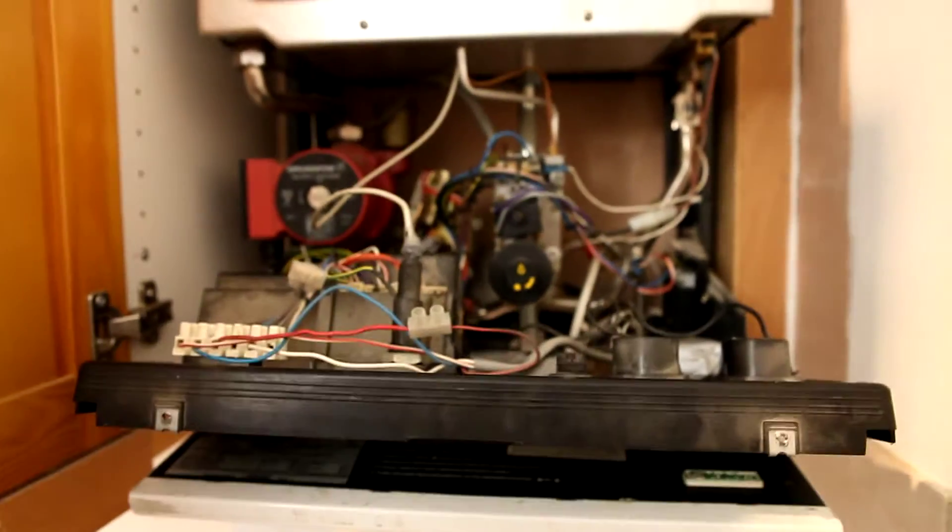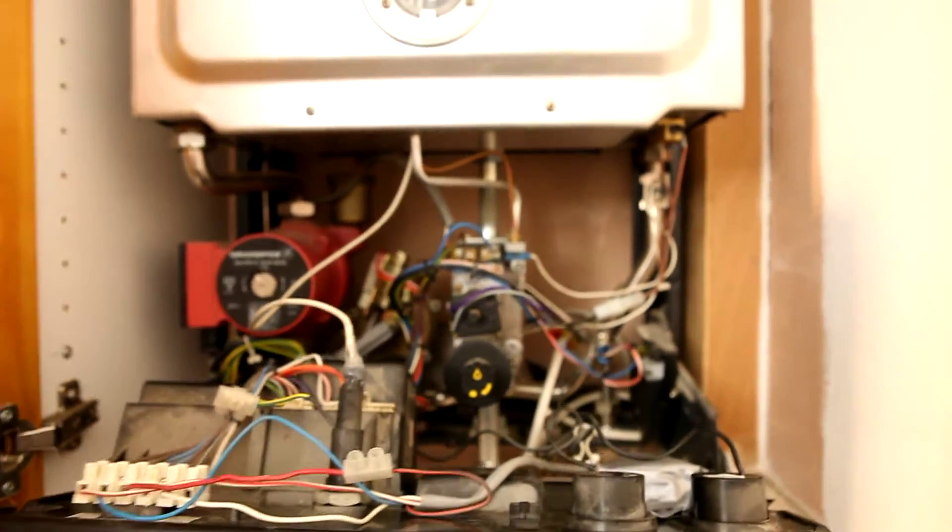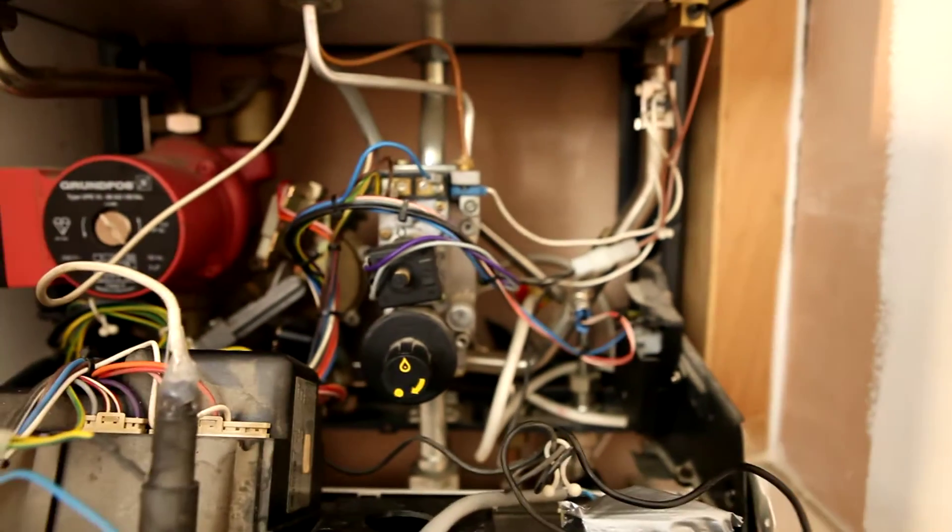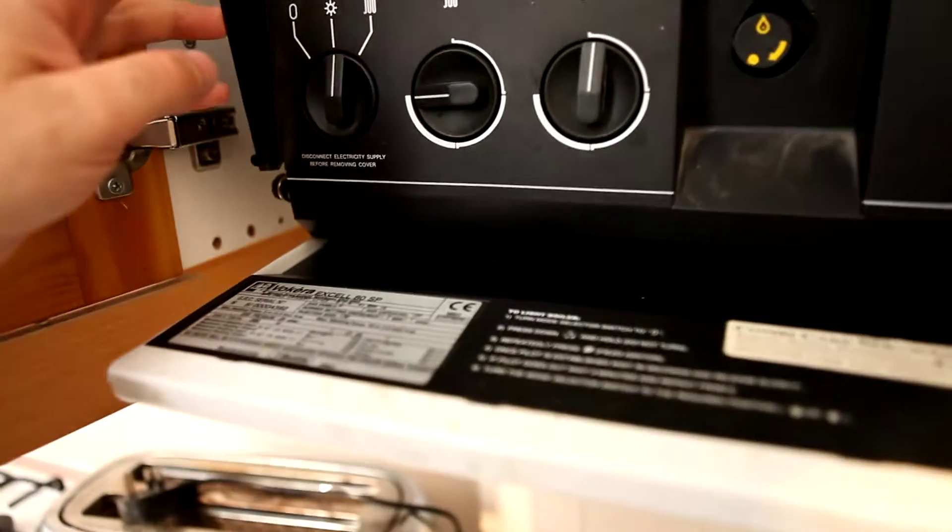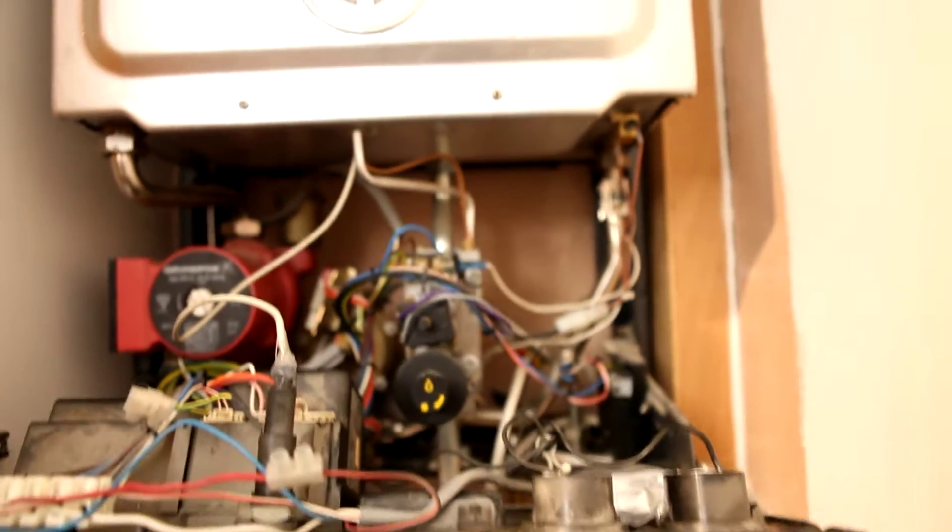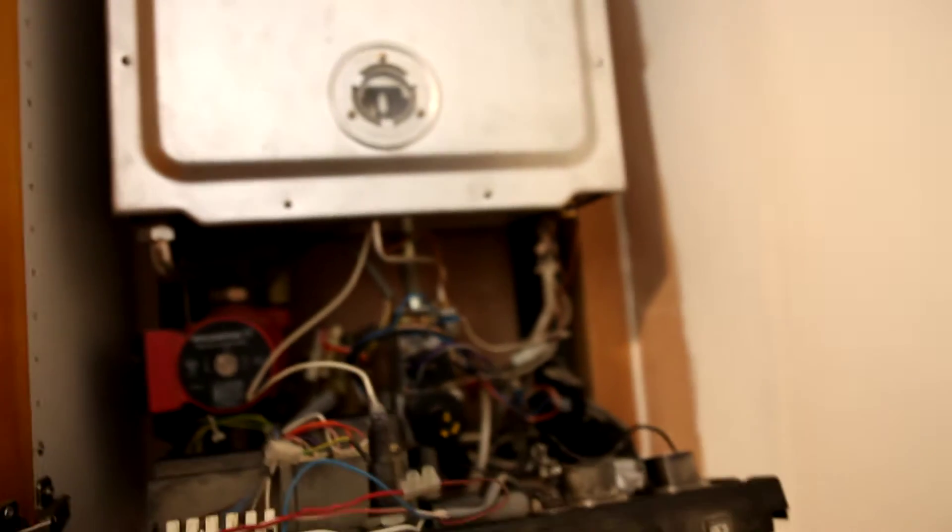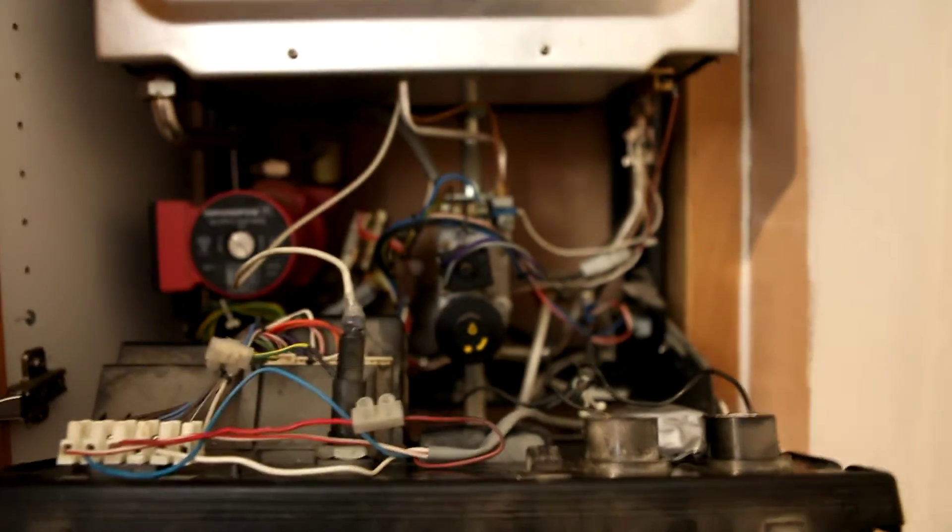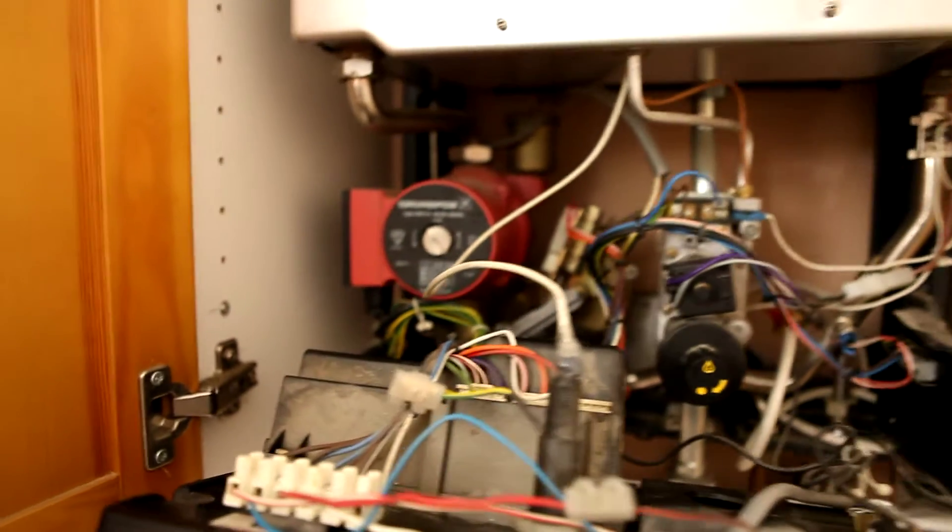I've had about three gas engineers in to have a look at this thing, which is an old Vokera, and it's a bit of a bizarre one, it's a Vokera 80, which is like 100,000 BTUs. 100,000 BTUs! That's 30-something kilowatts. This is a tiny two-bedroom modern apartment with double glazing everything. What on earth do you need 100,000 BTUs per hour for? That's madness! So the boiler's completely oversized.